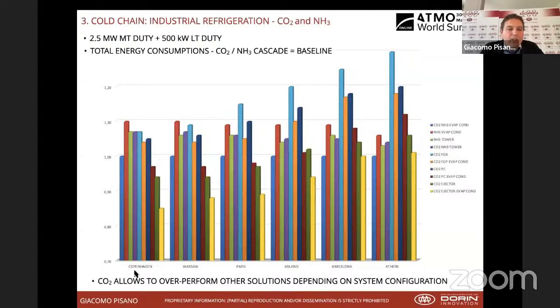For each climate profile, for each city, the benchmark has been set as the CO2 and ammonia cascade system with evaporative condenser. So you can see that the reference point set to one is always CO2 and ammonia with evaporative condenser. And you can see the other technologies, how they perform depending on the climate profile. For instance, in Copenhagen, very cold climate, the best performing system is, again, CO2 plus ejector and evaporative condenser. If you apply a standard flash gas bypass system to compare with CO2 ammonia cascade, you can see that this system is about 7% less efficient.